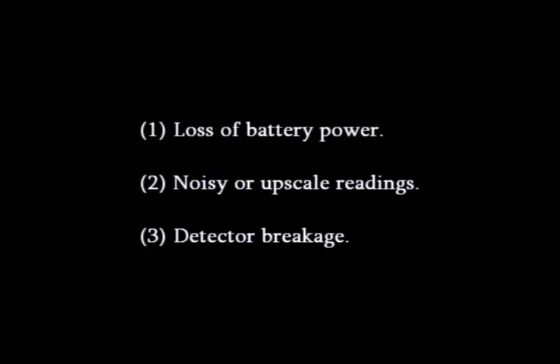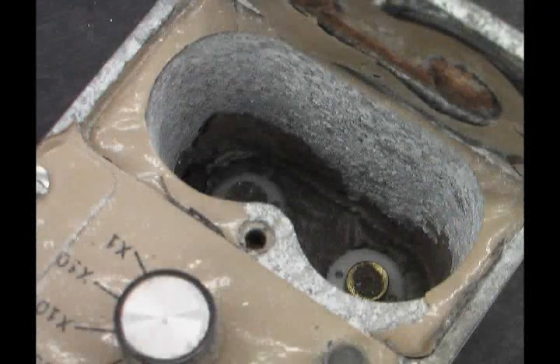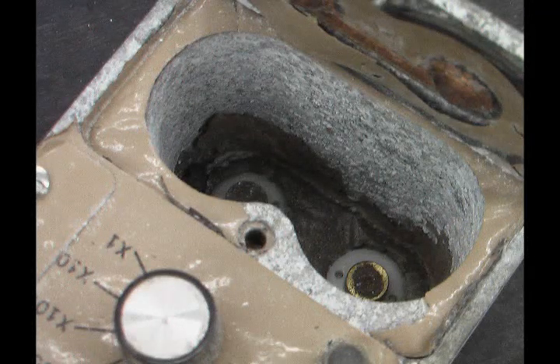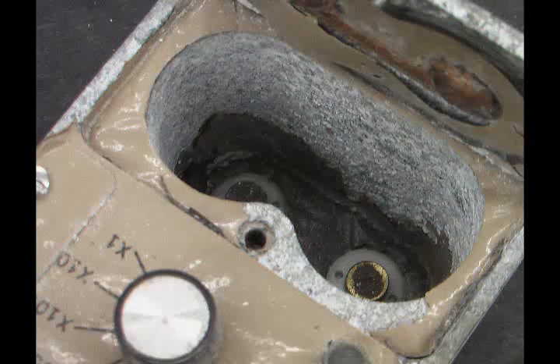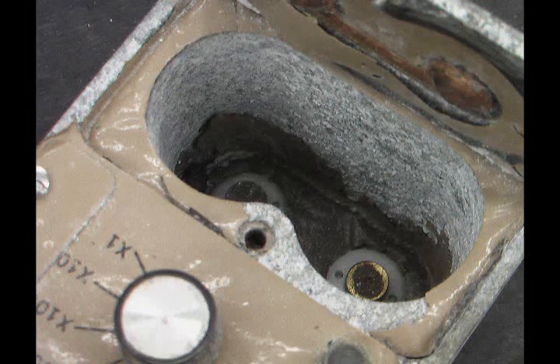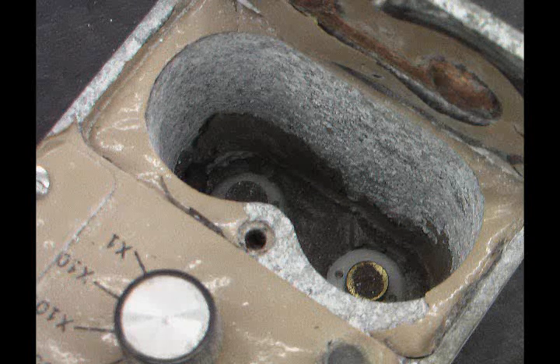The three most common repair problems with your Model 14C survey meter are loss of battery power, a noisy or upscale reading, and detector breakage. Loss of battery power can come from corrosion on the battery contacts caused by leakage of the battery acid. Avoid this by removing the batteries during storage. Fix the problem by scraping off and or washing the battery contacts with a diluted baking soda paste.